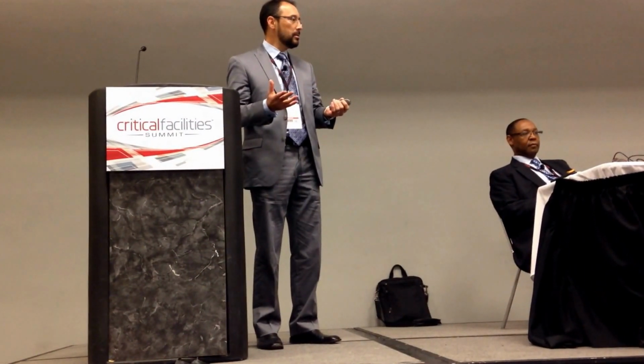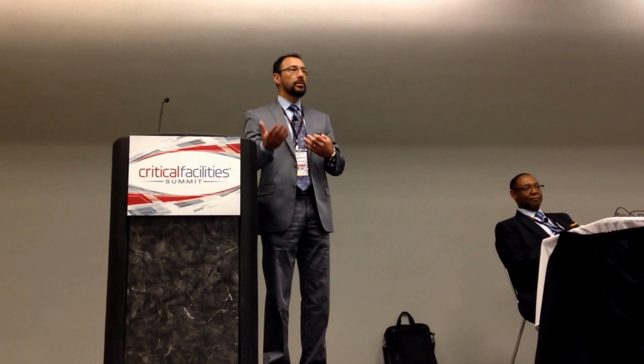Here's the problem within the data center, from an engineering and operational standpoint, summed up in one sentence: the facility is designed to support an IT configuration that it will never experience. You're designing something for a target that will never occur, so the design is essentially wrong from day one. That puts everyone on their back foot as soon as the doors open, constantly compensating for a wrong design. When I say wrong design, I don't mean it's anybody's fault, because the assumptions that go into the design are the best people can come up with at the time, but this is the reality of the situation.